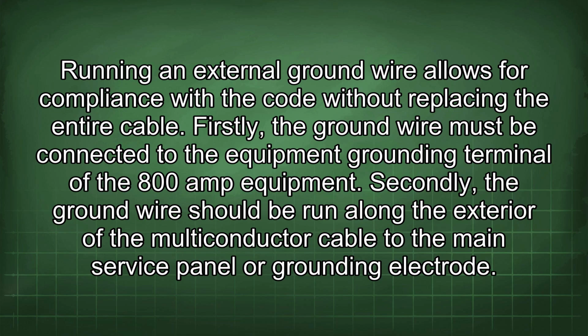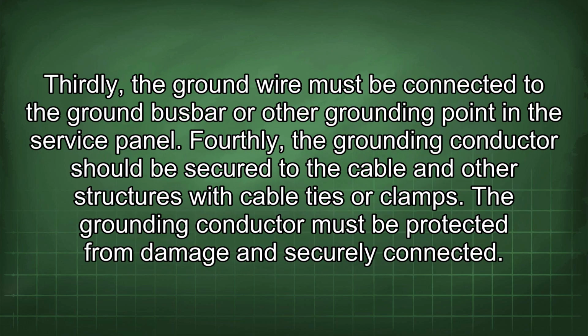Firstly, the ground wire must be connected to the equipment grounding terminal of the 800 amp equipment. Secondly, the ground wire should be run along the exterior of the multiconductor cable to the main service panel or grounding electrode. Thirdly, the ground wire must be connected to the ground busbar or other grounding point in the service panel. Fourthly, the grounding conductor should be secured to the cable and other structures with cable ties or clamps. The grounding conductor must be protected from damage and securely connected.